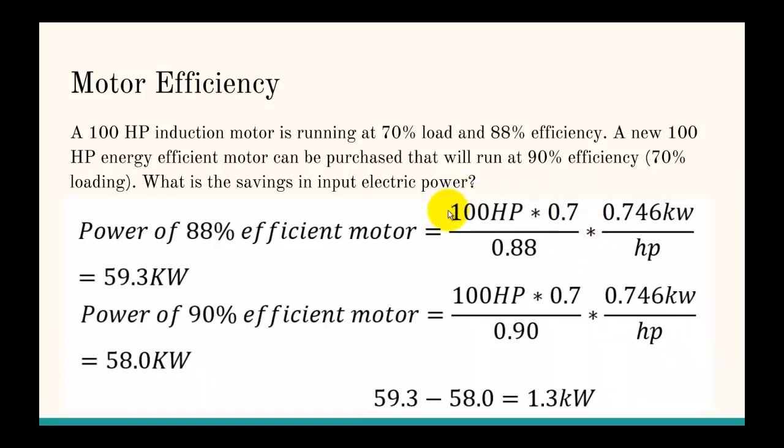This is basically 100 horsepower at full loading, so it outputs 0.7 of that, or 70 horsepower. Then you're dividing the output of the motor by the efficiency, and that gives you the input. Then you're converting horsepower to kilowatts using this unit conversion factor.